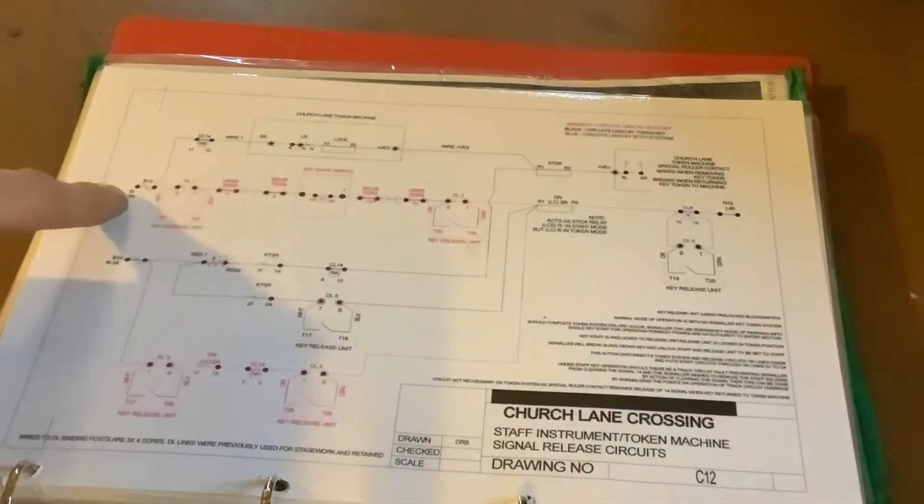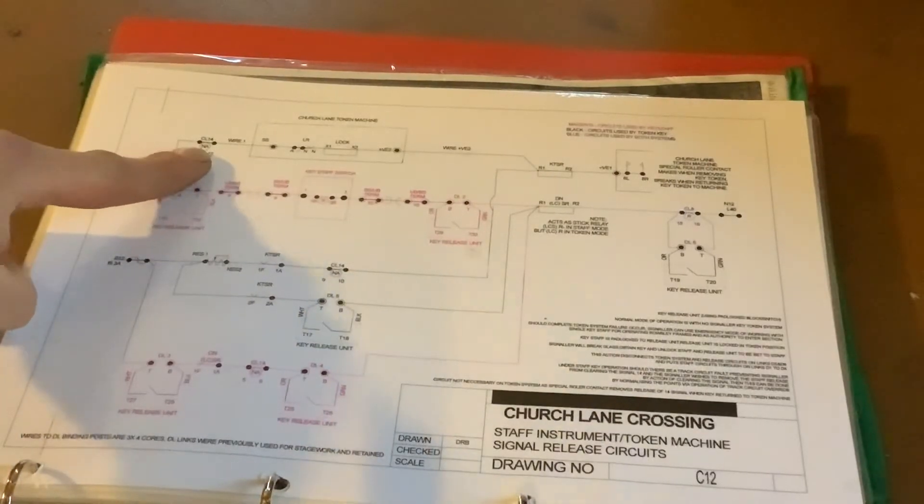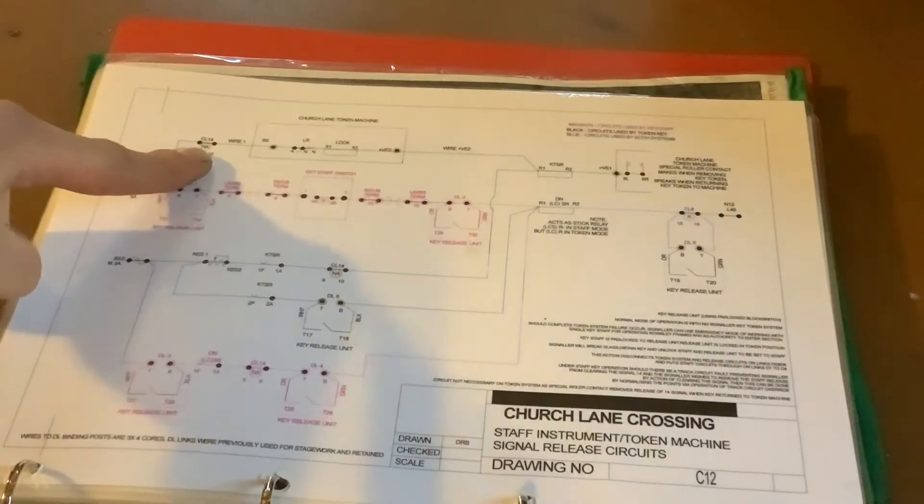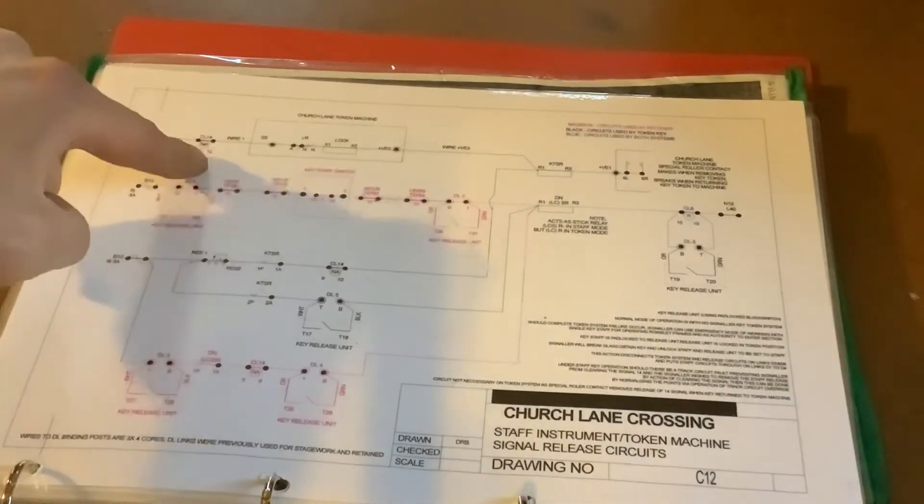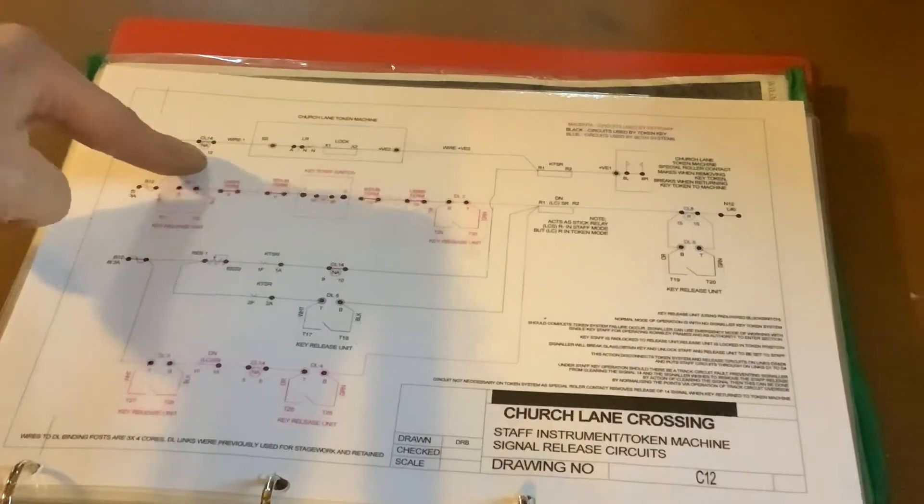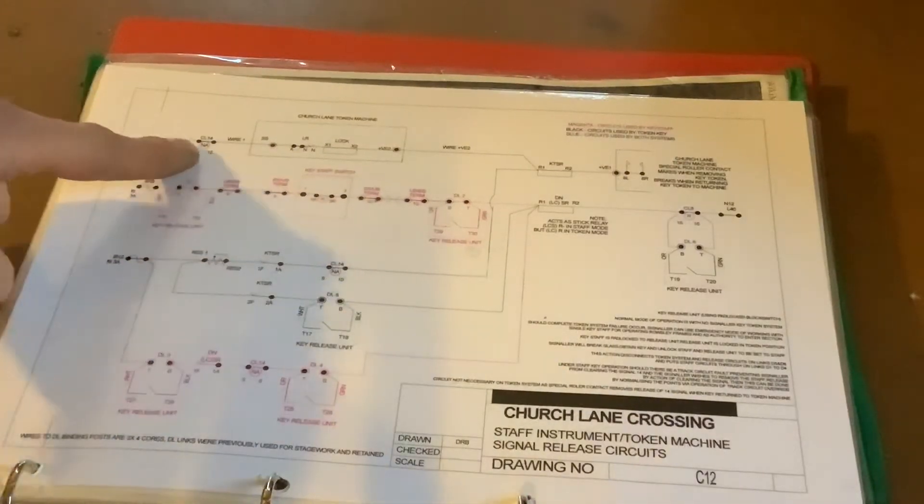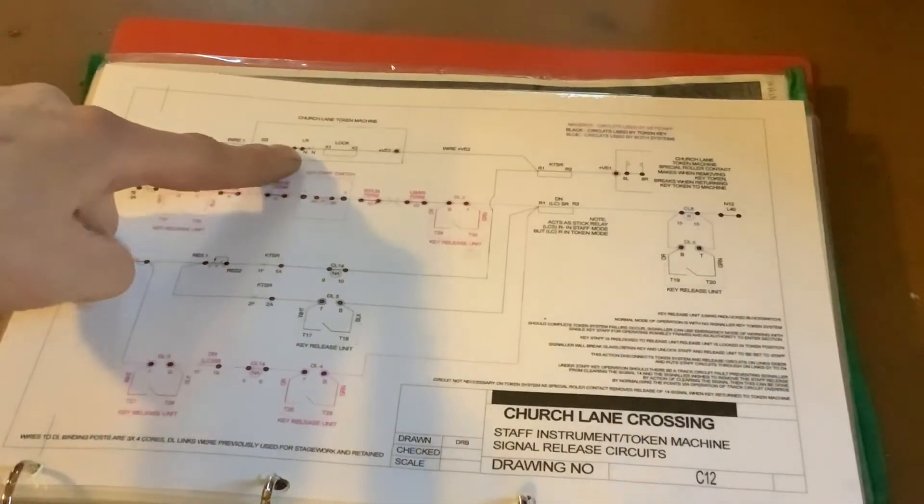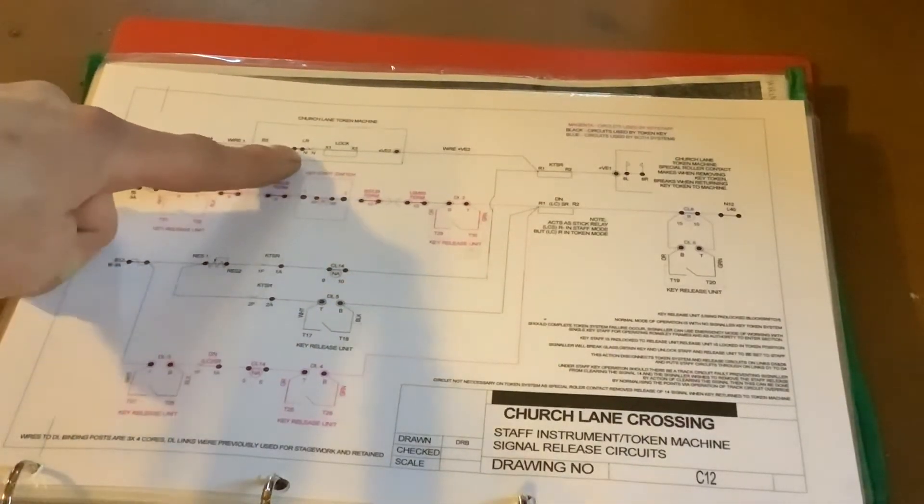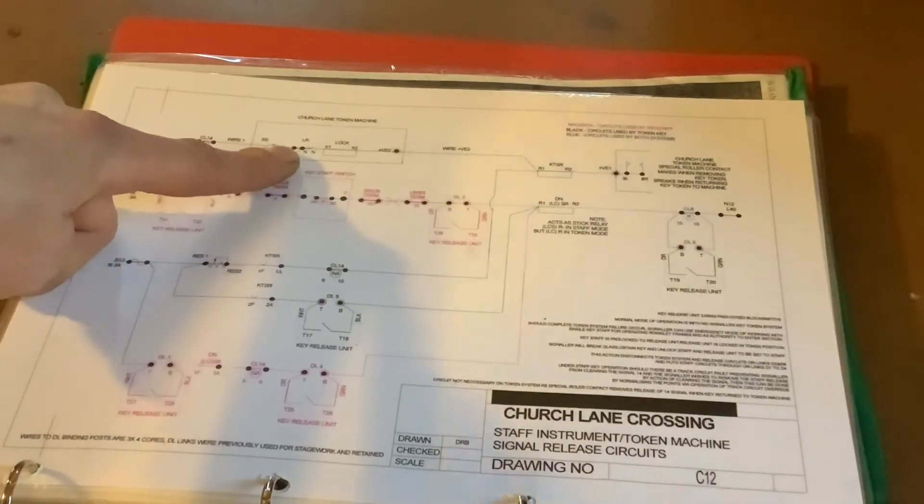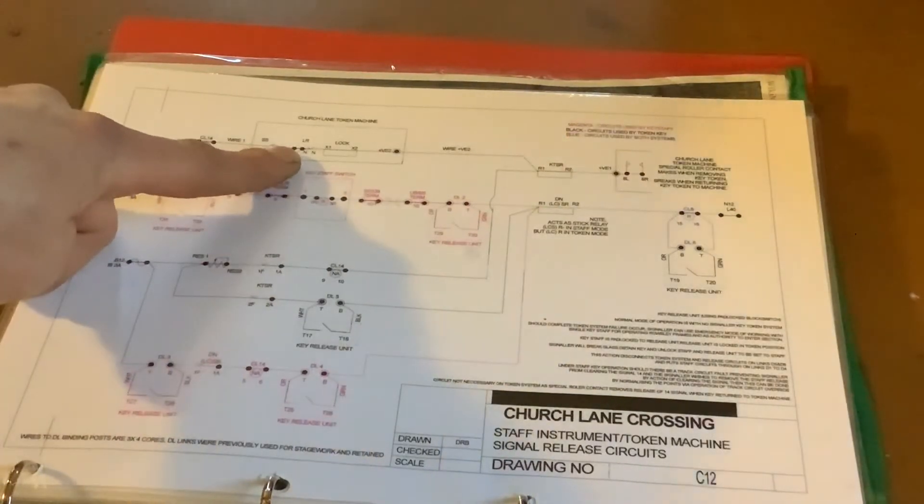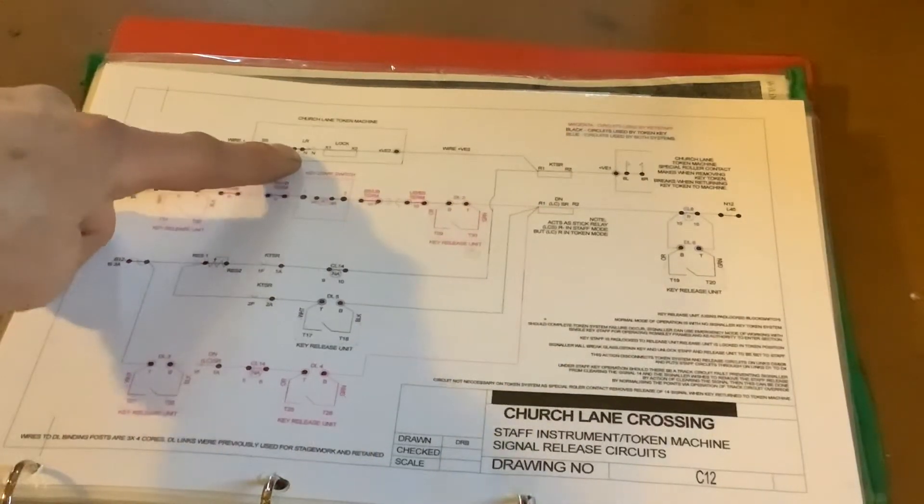So if we start here at our positive feed, we're going to take the top path now. This is our token path. First thing we'll notice is the contact of the starting signal, so again we must have placed our starting signal back to danger, same as we did in our key staff path. First thing we really reach is the lock relay inside the machine, proving that we can actually release a key out of the lock.